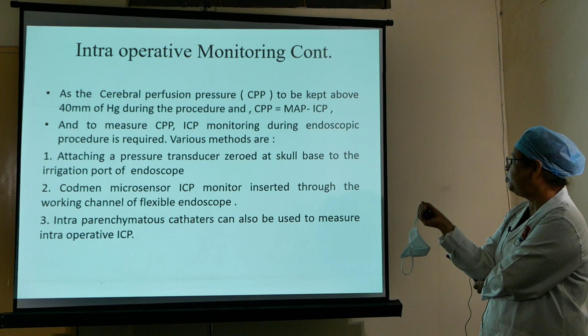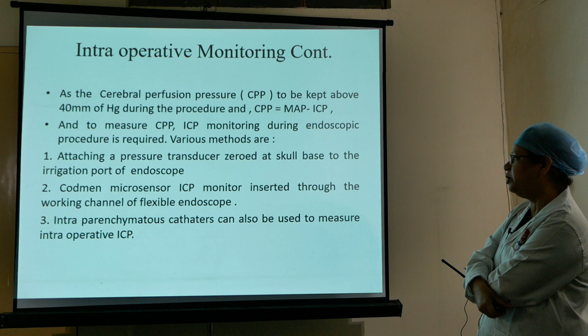To measure the cerebral perfusion pressure, ICP monitoring during the endoscopic procedure is required. So various methods to monitor are attaching a pressure transducer with a zero dead space to the irrigating port of the endoscope. The second one is a Codman microsensor ICP monitor inserted through the working channel of the flexible endoscope. And the third method is an intraparenchymal catheter. They can also be used to measure the intraoperative pressure.